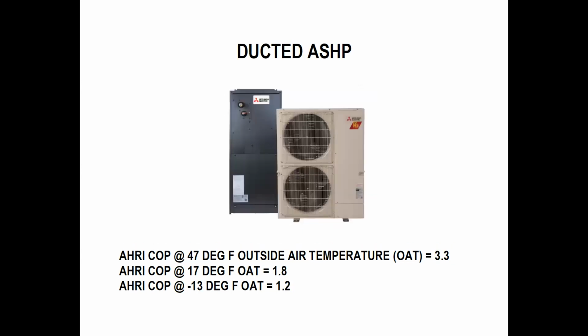All right, next page. All right, ducted. These are also heat pumps. They're not mini splits. They are split, the split being that there's refrigeration piping coming from the outside to the inside unit. The difference here is this is a ducted unit. It has ductwork that comes off and goes to the diffusers in the space. It is not as efficient because there's energy associated with moving that air through the ductwork. There's friction losses, so it's not as efficient a unit.